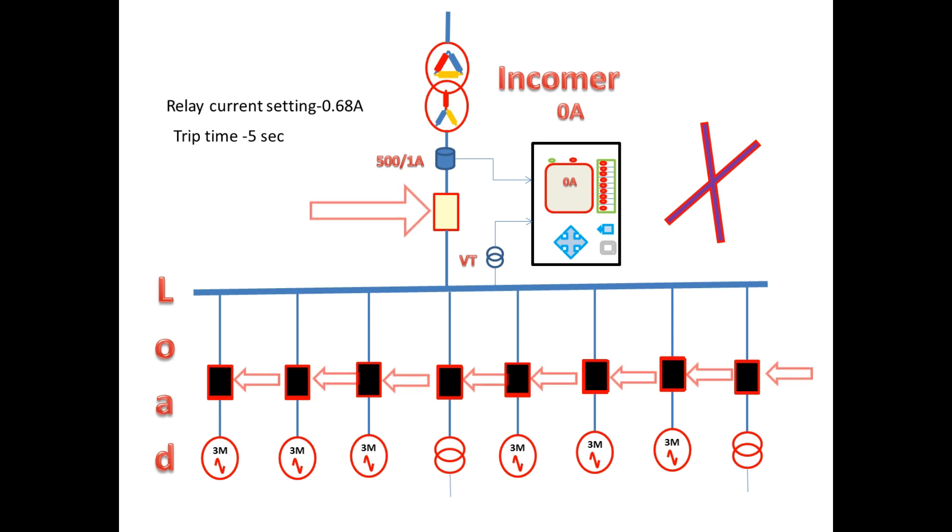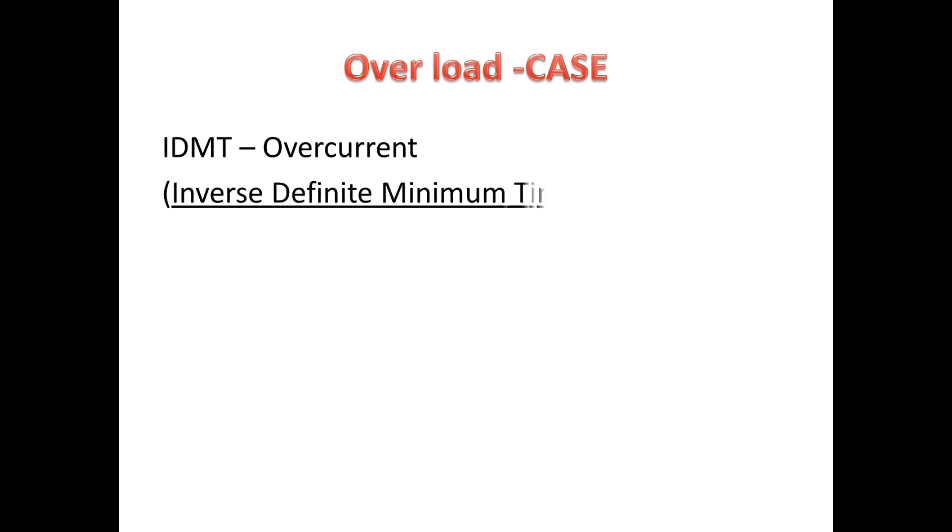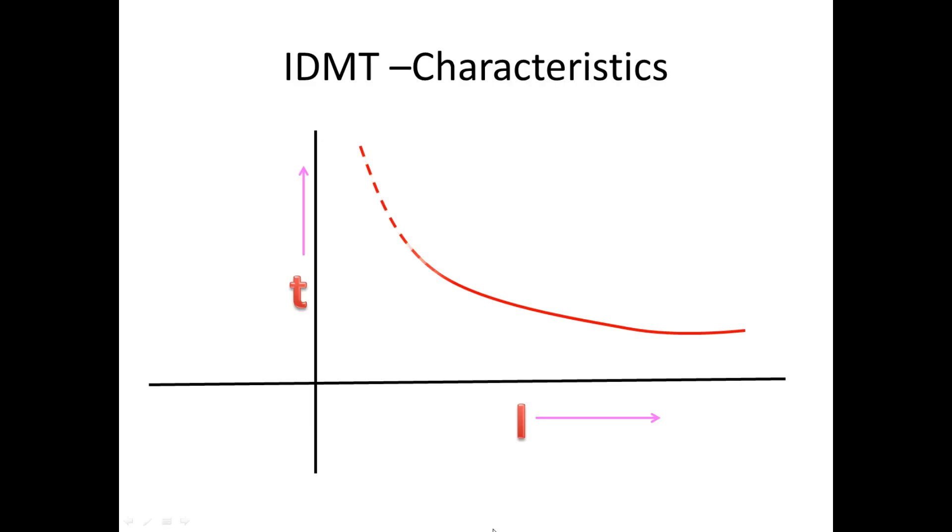Because the incomer has to give chance to trip outgoing first, then only it has to take its own chance. In order to overcome this problem for overload case we have curve based trip, i.e., IDMT. The full form of IDMT is Inverse Definite Minimum Time. This tripping characteristic will be like this: when the current increases, the tripping time will get reduced.